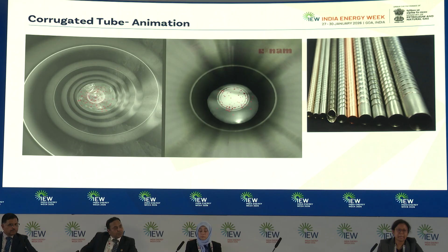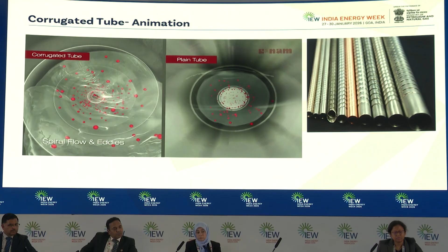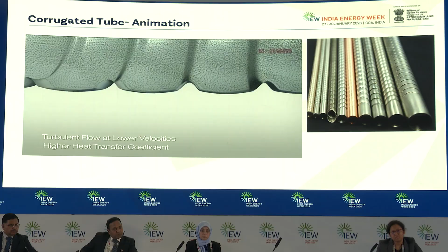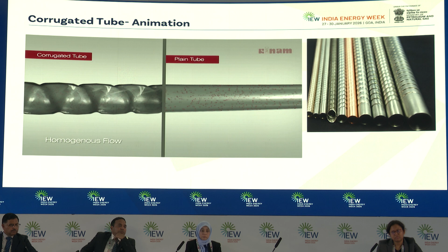The helical indentation imparts two flow regimes to the fluid in the corrugated tube, spiral at the core and eddies at the periphery. Thus, corrugated tubes induce turbulence in the fluid even at lower velocity at the peripheral layer, which results in a higher heat transfer coefficient. The two-regime flow enables thorough mixing of the fluid, ensuring a homogeneous fluid mass rather than a layered flow pattern.